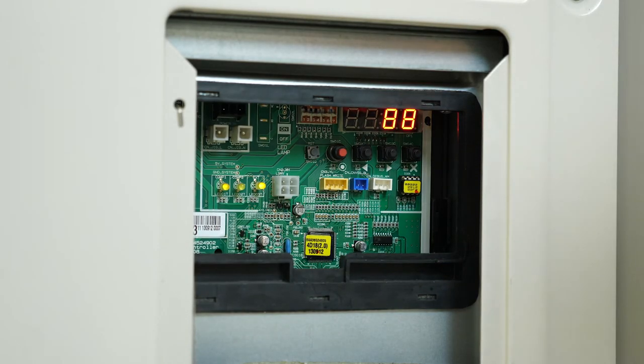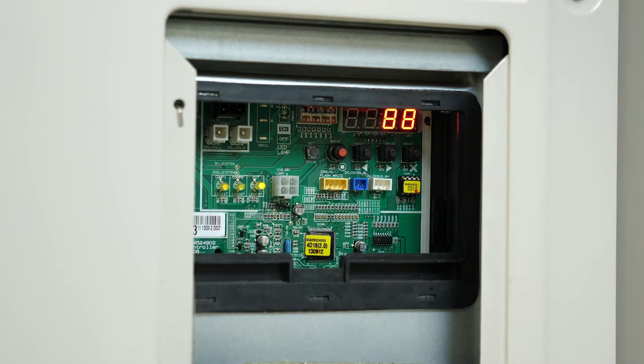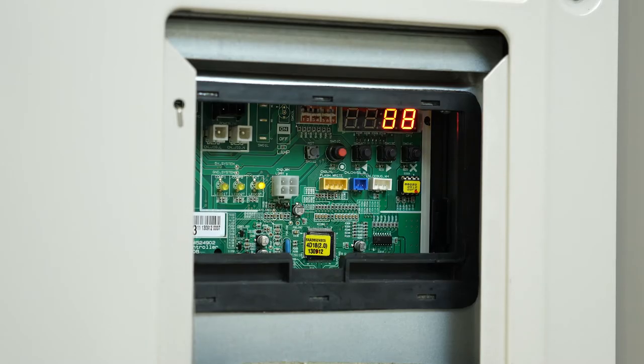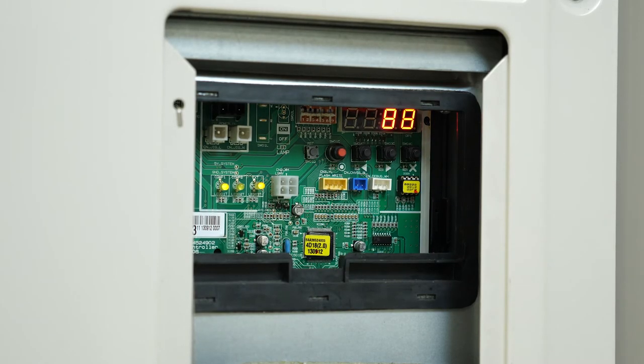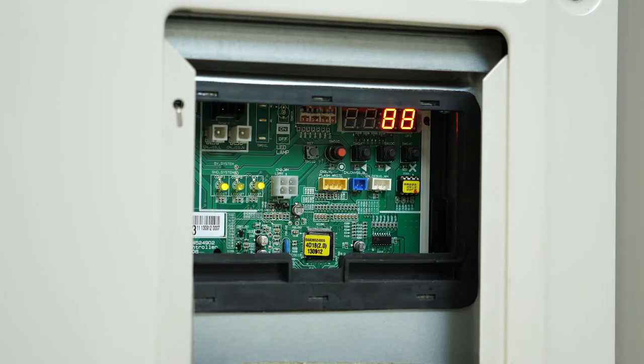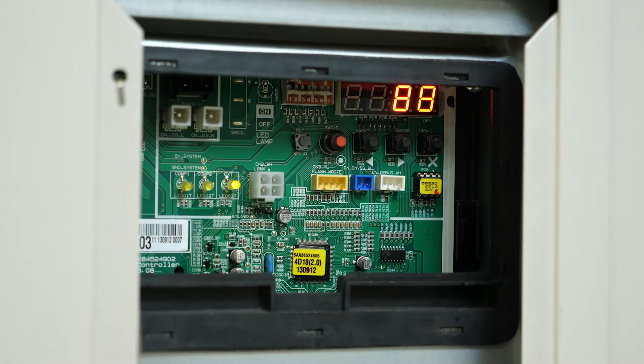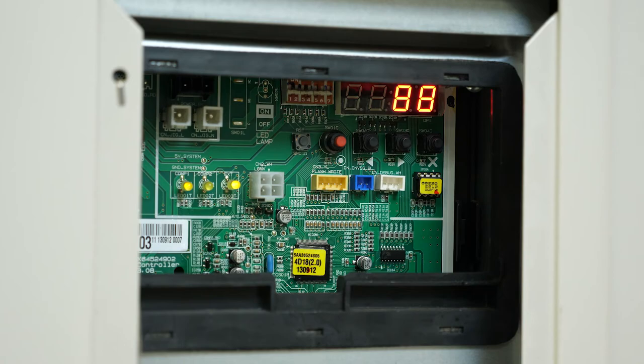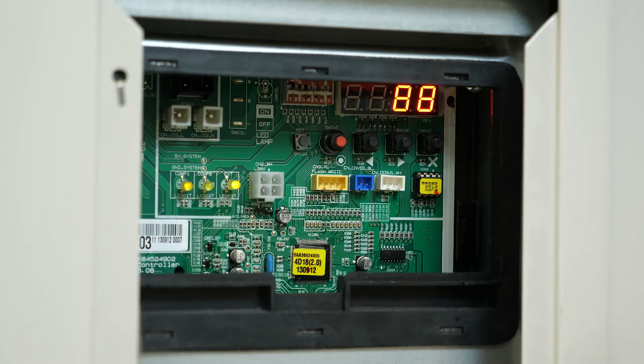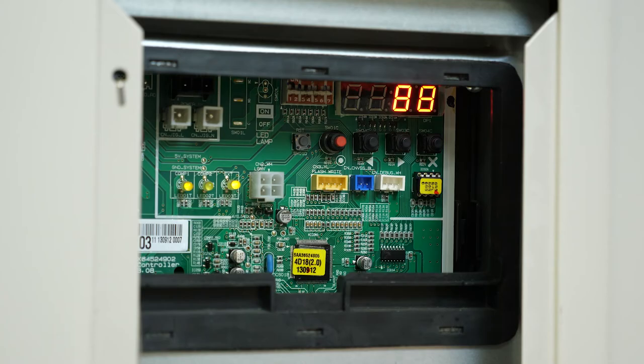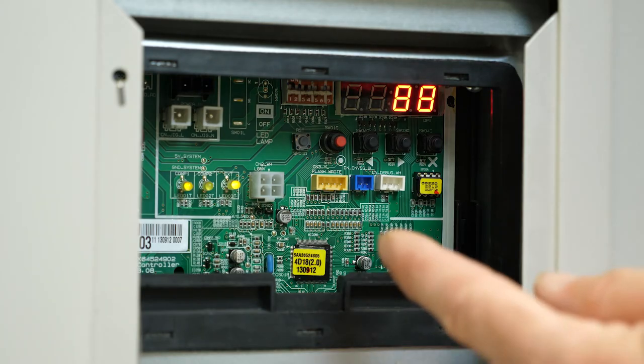88 is on, we know the process is going through. During this auto address process, 88 will stay on the screen until it shows us the correct number of indoor units and the correct number of HR boxes. If those two numbers are correct for the system you're working on, then you know the auto address has correctly found all your indoor units.